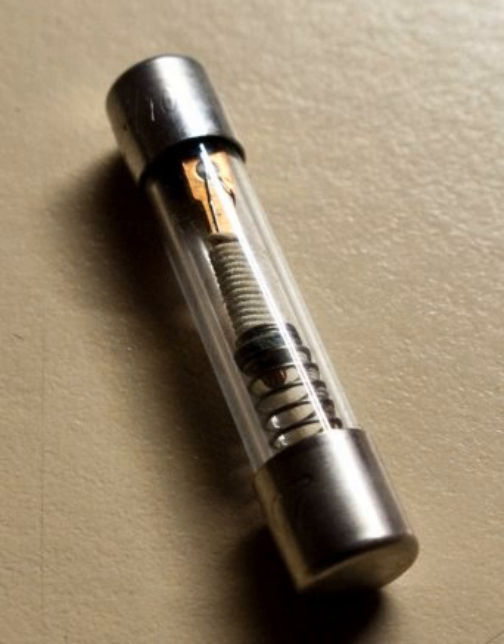UL 248 currently has 19 parts. UL 248-1 sets the general requirements for fuses, while the latter parts are dedicated to specific fuse sizes, such as 248-8 for Class J, 248-10 for Class L, or for categories of fuses with unique properties, such as 248-13 for semiconductor fuses, 248-19 for photovoltaic fuses. The general requirements 248-1 apply except as modified by the supplemental part 248X. For example, UL 248-19 allows photovoltaic fuses to be rated up to 1500 volts DC versus 1000 volts under the general requirements.